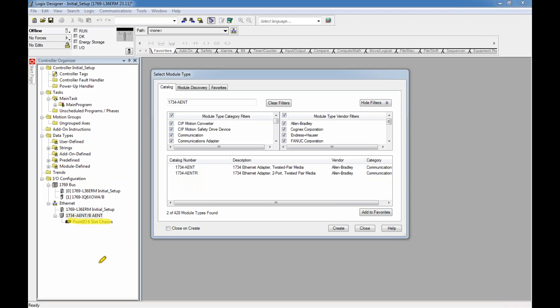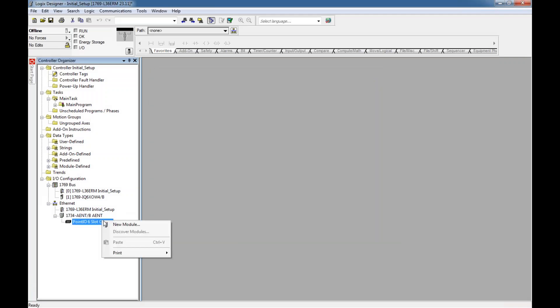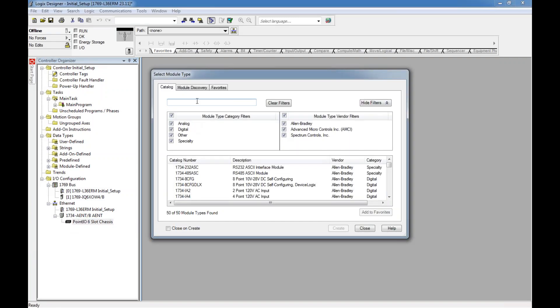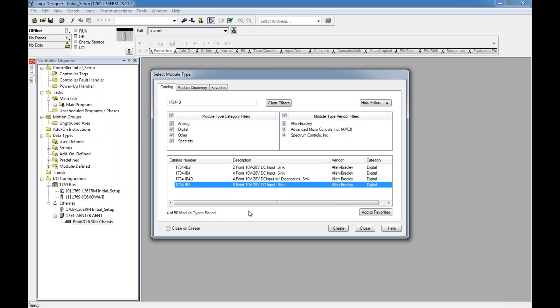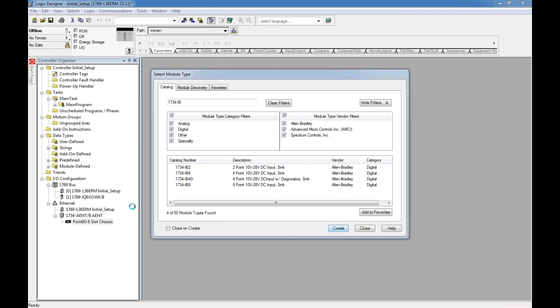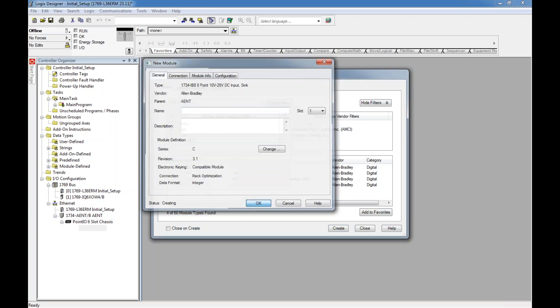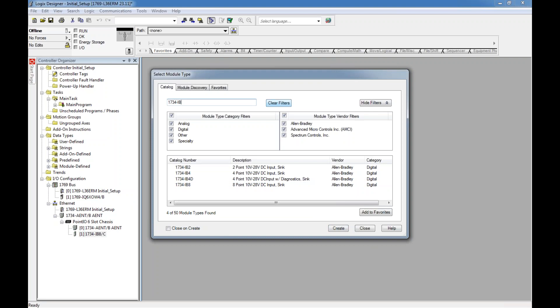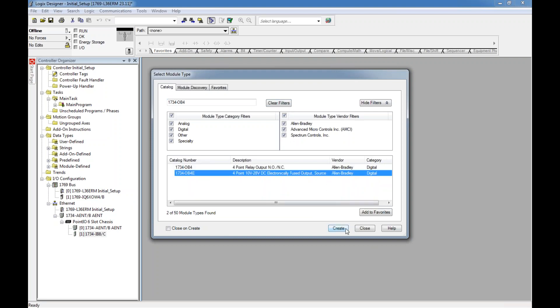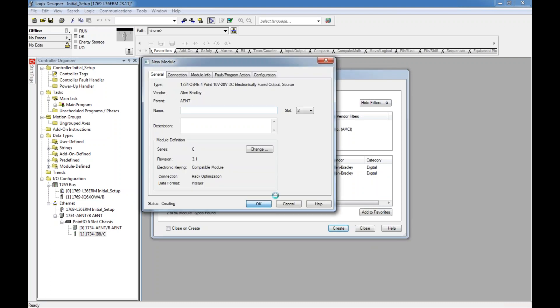I'm not done yet — I have to right-click on the Point IO six-slot chassis and add input and output cards. I click New Module and add the input card: IB8 sinking input module. Hit Create, hit OK. Then I add OB4E for the output module and hit Create. I've now entered my inputs and outputs.